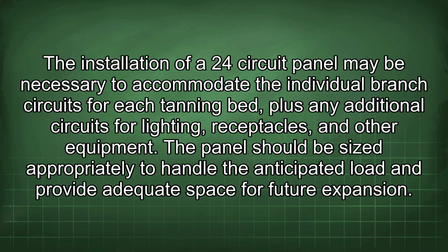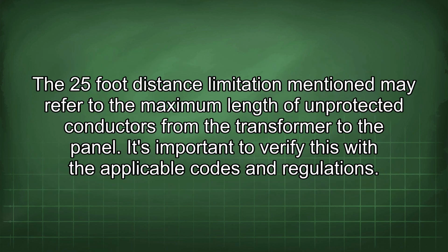The installation of a 24 circuit panel may be necessary to accommodate the individual branch circuits for each tanning bed, plus any additional circuits for lighting, receptacles, and other equipment. The panel should be sized appropriately to handle the anticipated load and provide adequate space for future expansion. The 25-foot distance limitation mentioned may refer to the maximum length of unprotected conductors from the transformer to the panel. It's important to verify this with the applicable codes and regulations.